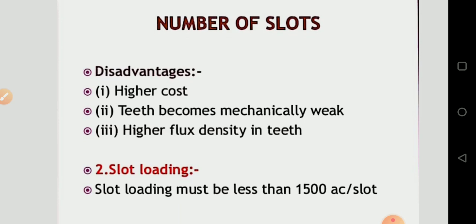A higher number of slots has some disadvantages: higher cost, teeth become mechanically weak, higher flux density in the teeth, and slot loading must be less than 1500 AC per slot.